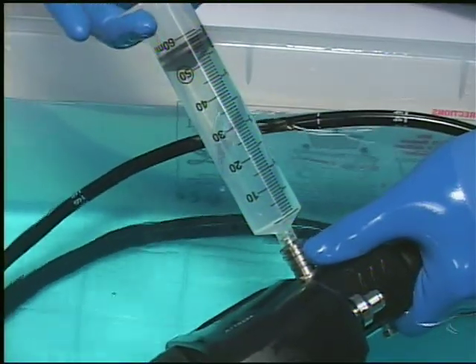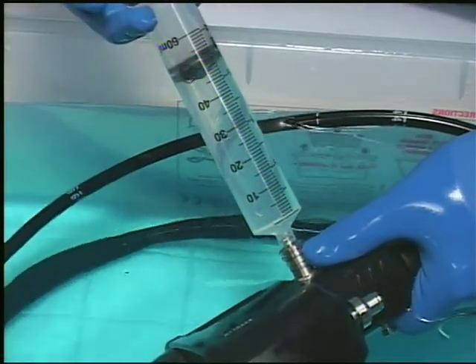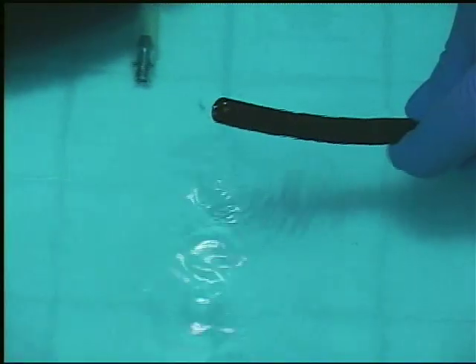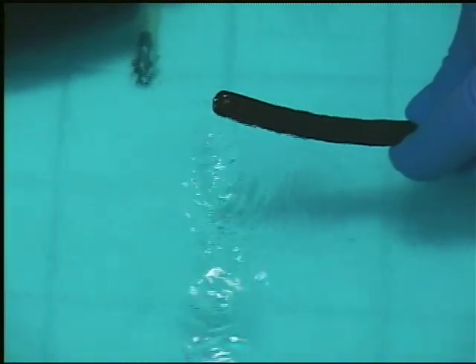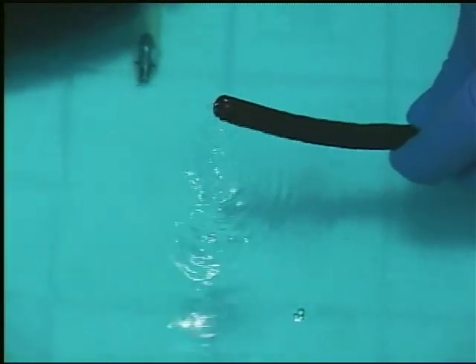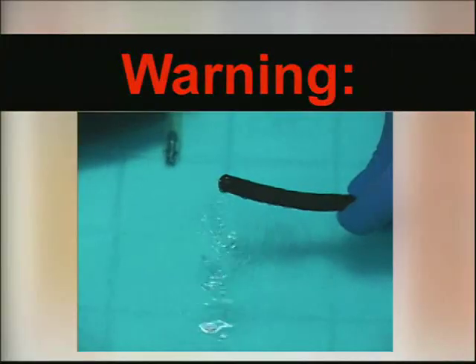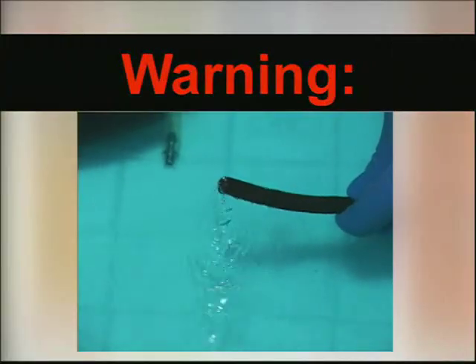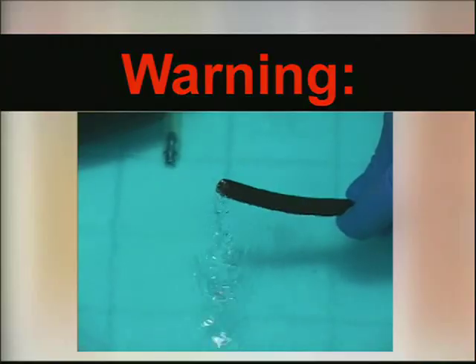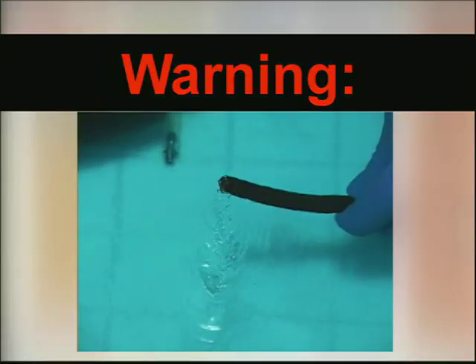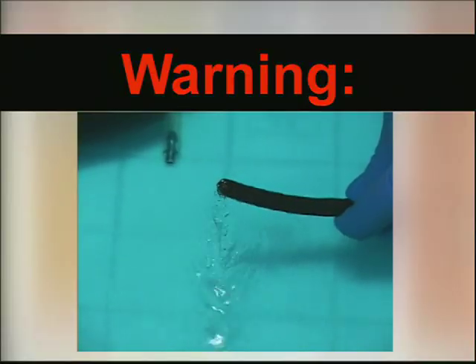Fresh or reused actively effective disinfecting solution should be flushed through this connector and will simultaneously flow through both the air and water channels of the scope. Warning: avoid introduction of air during the flushing process. Confirm that no air bubbles exit the channel openings at the scope distal tip. The presence of air bubbles could prevent contact of the disinfectant with channel surfaces.